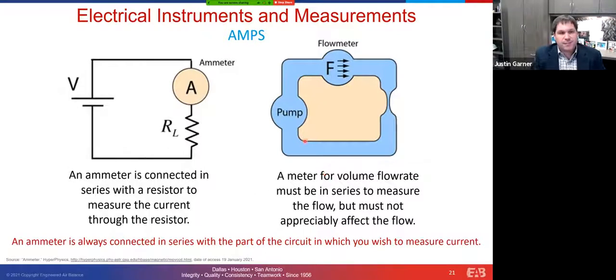Amperage is the opposite. Amperage is flow. And so if you were to look at a pumping system like this, just like if we were to measure volumetric flow rate in a hydronic system, we're going to need to insert a meter that actually measures flow inside the system, in line with the flow, right? You're going to have to do the same thing with an amp meter. If you were to directly measure amperage in a circuit, you actually have to split the circuit and measure across it with your meter. That's not exactly how our current clamps work. They use a transformer type principle with a coil to do the same thing, but you are measuring in series in the circuit. I think I said parallel earlier, but it's actually in series. So just be aware of that.